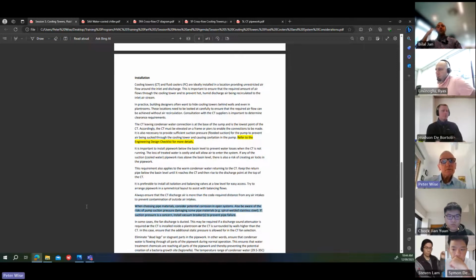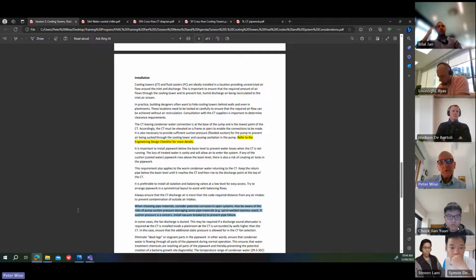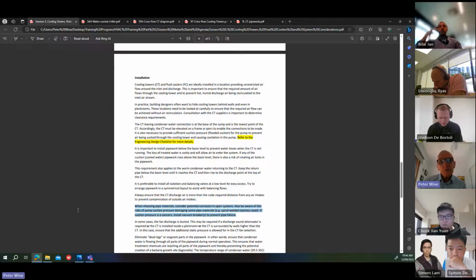When choosing pipe materials, consider the potential corrosion in open systems. So for a closed system, if you're using a fluid cooler, you haven't really got any concerns with corrosion in the pipework. So you can use steel pipe, for instance, if it's a large system. Normally you'd use copper pipe up to a certain size, and then you'll go to steel if it's, say, above 150 millimeters. But with a cooling tower, because you've got potential corrosion, once again, you'd use copper up to 150, and then you might use stainless steel above that. But steel is at risk of corrosion if you use that in an open system.